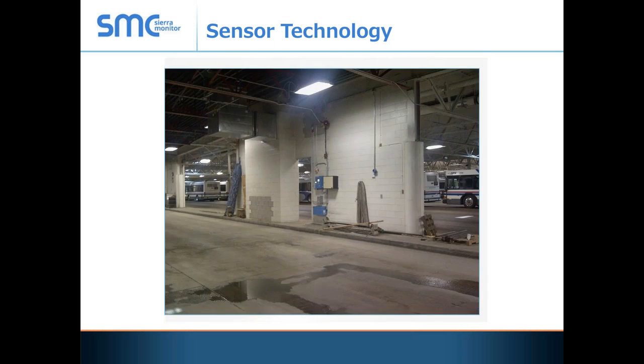Here is a controller on the wall with a battery backup and its charger. This brown cabinet contains all the calibration tubes for the 32 sensors located on this controller. This allows a technician to come in every year, attach calibration gases right here, and send gas up to the sensors without disrupting bus operation, traffic, or normal facility operations. This reduces calibration time significantly. This is a big recommendation because calibration can sometimes disrupt facility operations — this method is pretty much the way to do it.